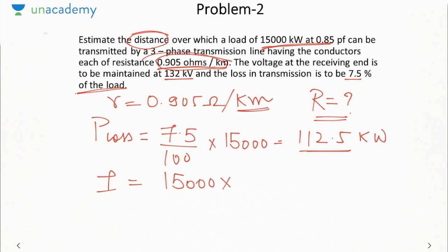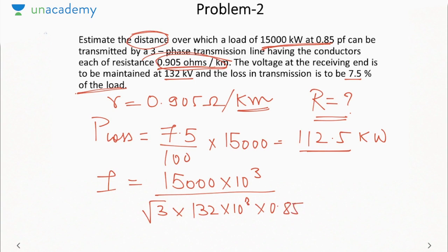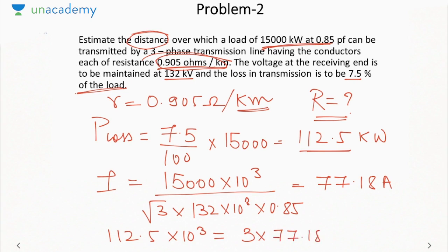15,000 kilowatt by root 3. We are given the receiving end voltage also and the power factor also 0.85. So this current comes out to be 77.18 ampere. Now transmission line losses 112.5. This will be I square R, but remember it will be 3 times I square R for 3 phase. This factor of 3 is the most common mistake. So from here I can calculate resistance.